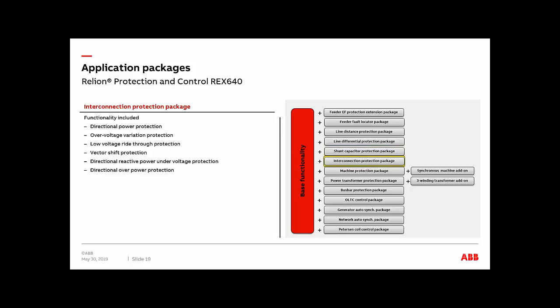Now moving on to the interconnection packages. Here you're going to have your directional power protection, 32. Then you're going to have your overvoltage variation protection, and this is mainly used as an application of voltage quality. That's supplied by the utility, and it pretty much evaluates the power quality by calculating the average RMS in a period of time of 10 minutes. So it will know what the utility is providing. You can use it as an alarm, mainly in this case.